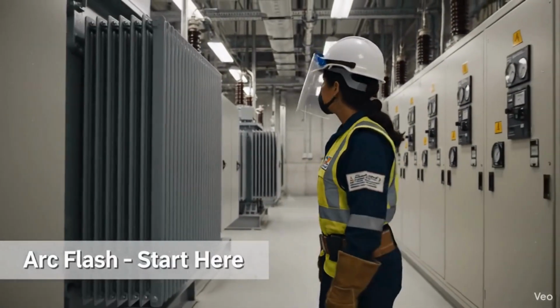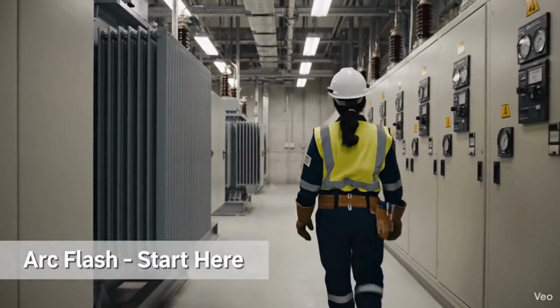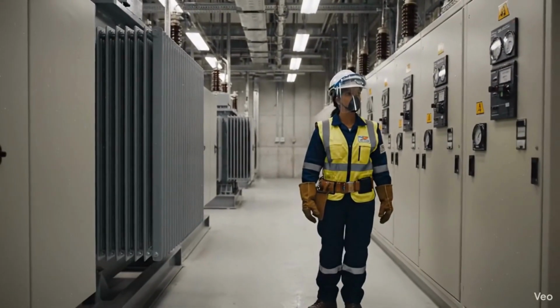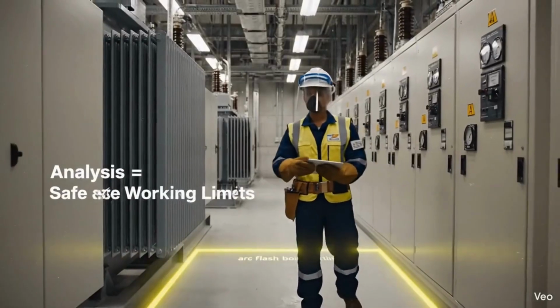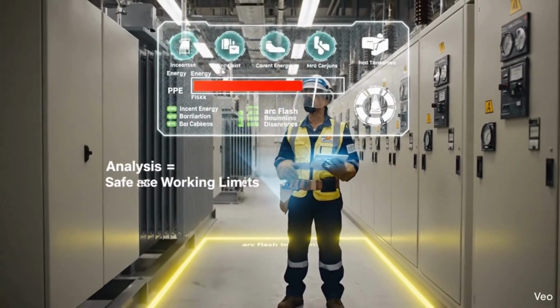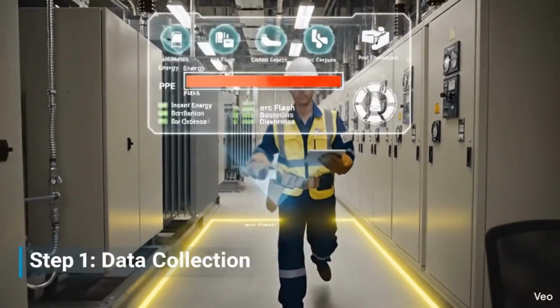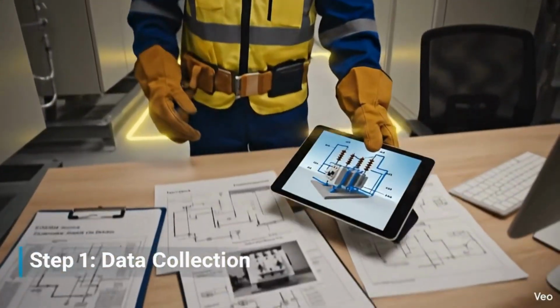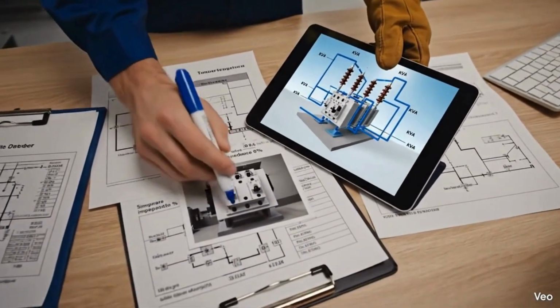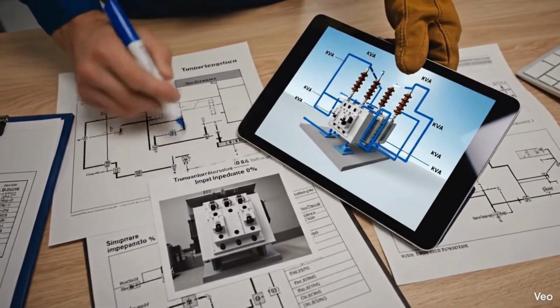Arc flash hazards begin where power is concentrated, so we start at the source, the electrical room. Arc flash analysis identifies the energy levels and boundaries needed to keep technicians safe. Arc flash analysis begins by collecting system data, like transformer ratings, breaker settings, and cable details.